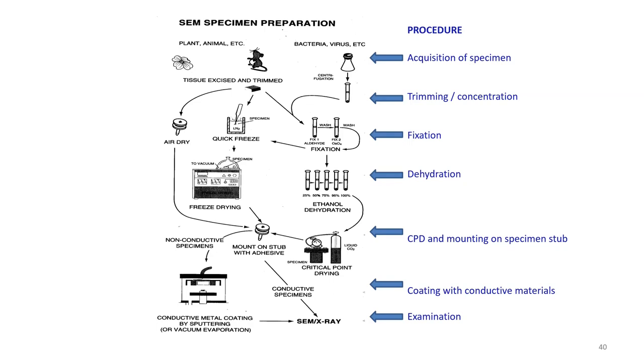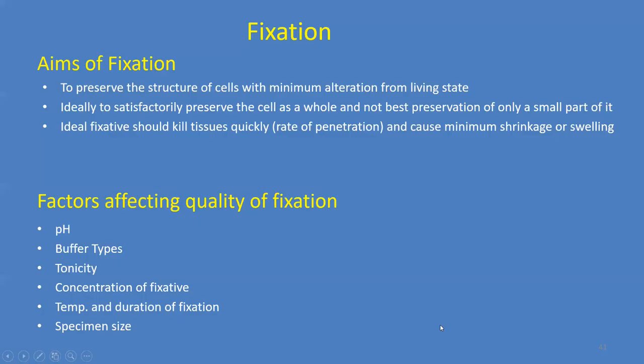You're interested in the surface features, and if it is shrunken, then it won't give you the information you're looking for. So there is a special procedure called the CPD, or the critical point drying method. And after this, you have to make the specimen conductive. For that, you have to have a metal coating, typically with gold palladium. It's an instrument called the sputter coater, and then you examine your specimen.